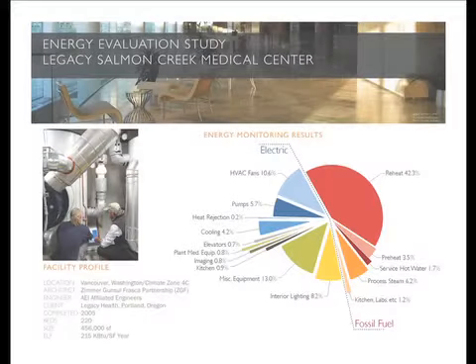So we started looking around, finding information, and what we found out is that the primary energy use in hospitals was for heating. And it was dominantly in a building that almost doesn't need heat, because the amount of energy input would seem to indicate that the amount of energy being used in here, and most of it being given off as heat, that it wouldn't need heat. But it was primarily using gas for heat. And it was, as this slide can show, it was for reheat.